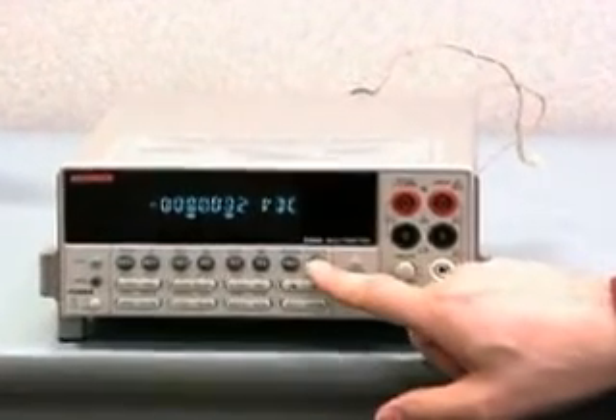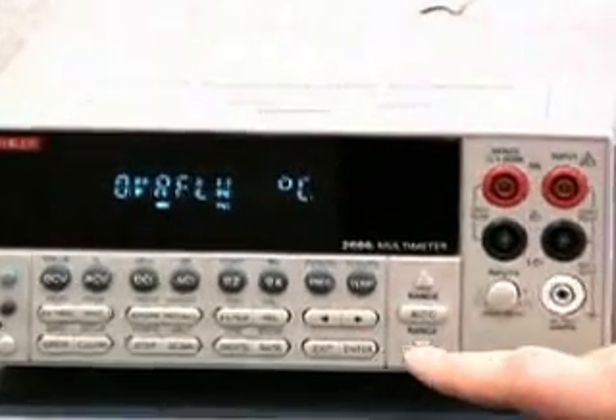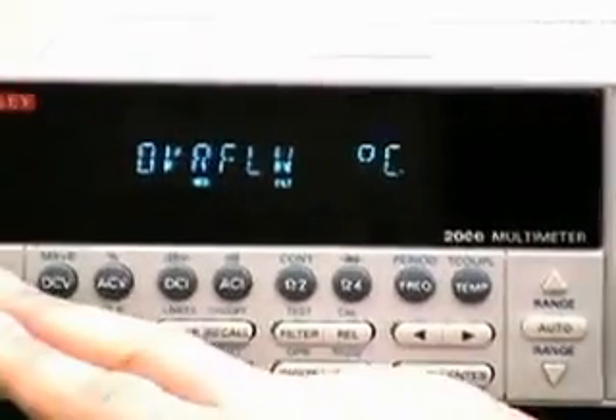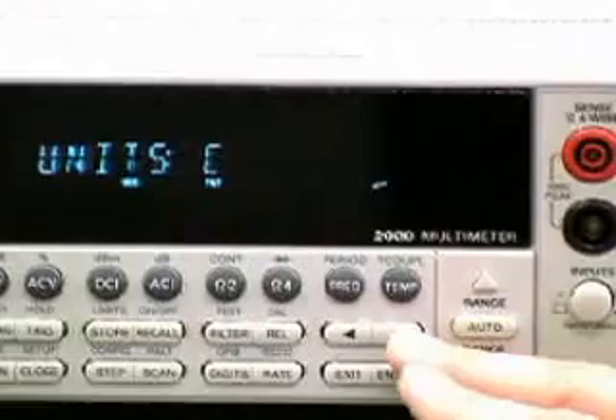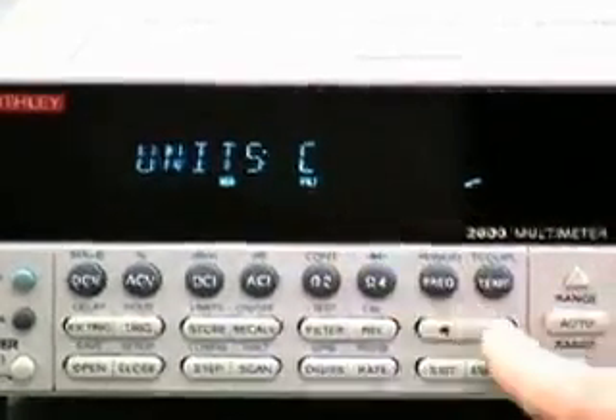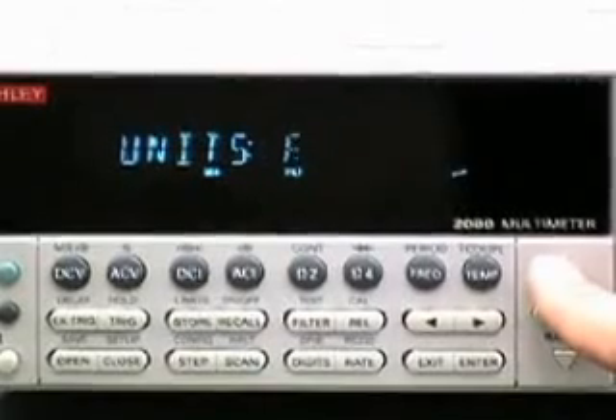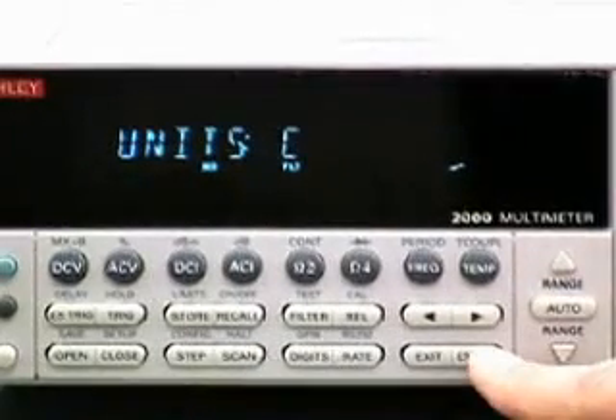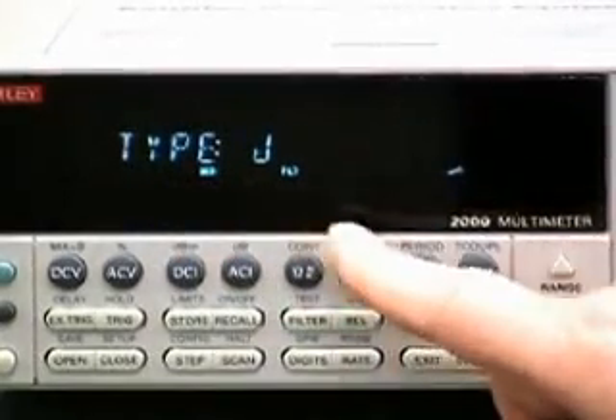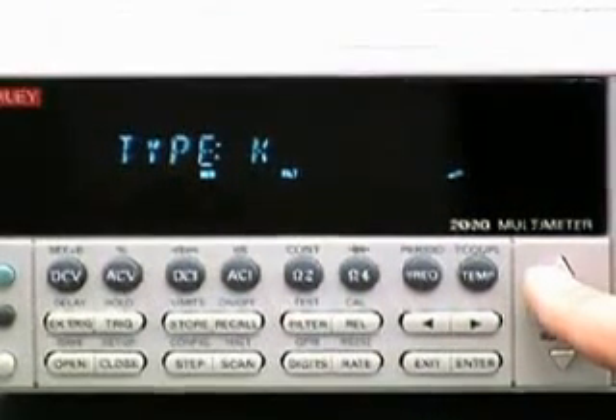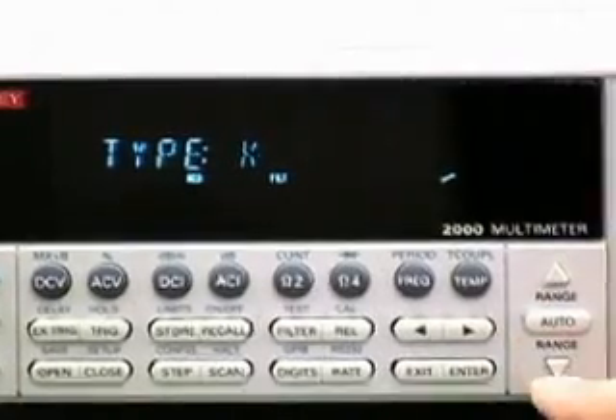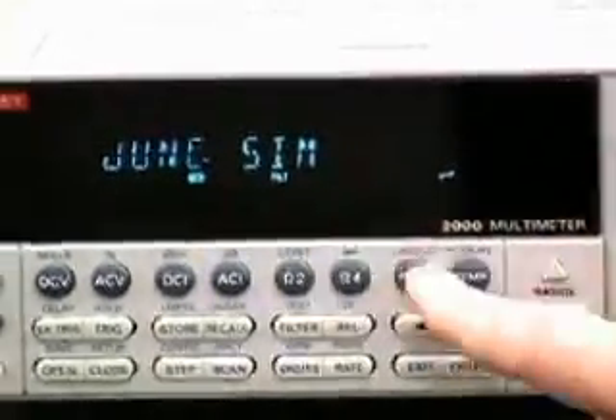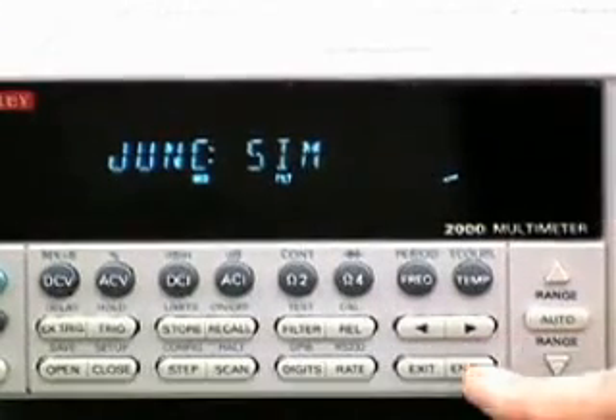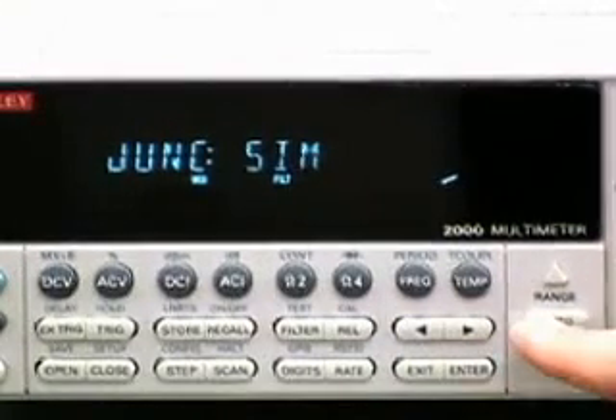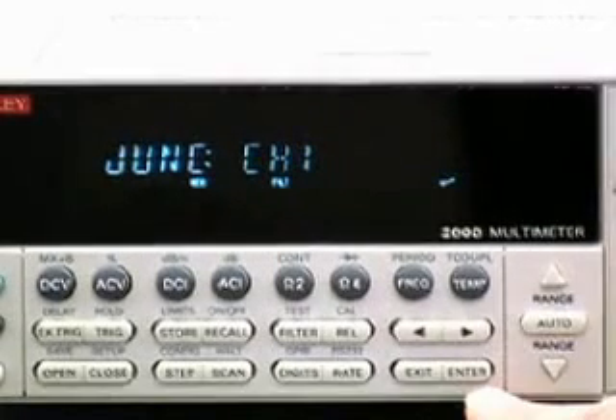I'm going to go to the display and put it in temperature, right here. We'll set up temperature. Very easy to do. Shift, temperature. We want the units in degrees C. You have your choice of degrees C, K, or F. We'll go with C, hit enter. Then the different types of thermocouples. Notice there's type J, K, T. We happen to have a type K hooked up. Enter. Then the junction simulated. That means you simulate what you think the cold reference is, but in this case, we know it's on channel 1, so we'll select channel 1.